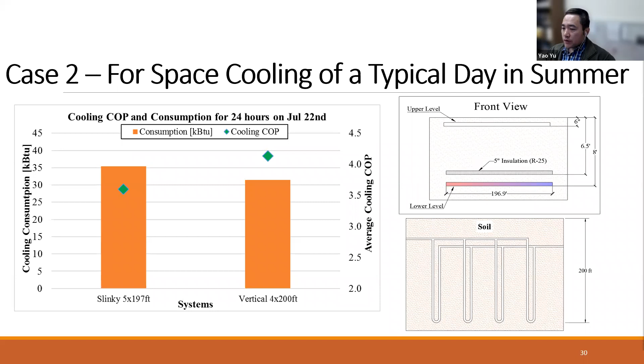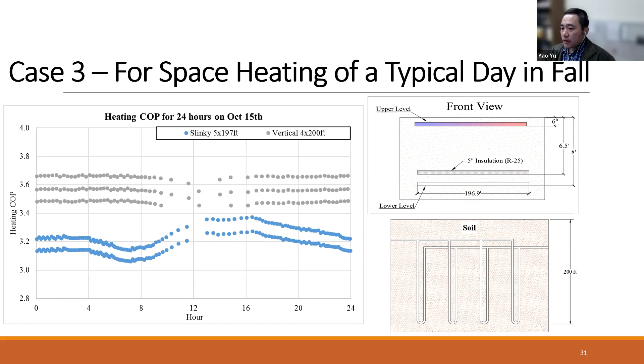So this slide shows the heating COPs of the heat pump for a typical day in the fall season, where the upper loop is used for space heating. As you can see, the heating COP of the heat pump using the vertical boreholes is relatively stable and is not affected by the ambient temperatures.